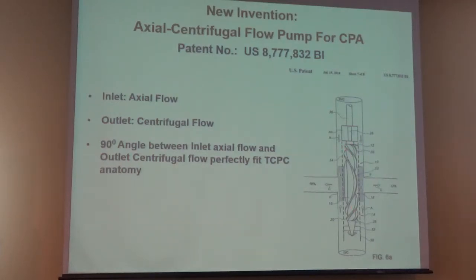When you pump, it runs very fast. So any kind of axial flow pump, HeartMate, anything, when you run very fast, they generate a centrifugal force very, very significantly. And then they will pump from here and here. Since the delta P in failing Fontan circulation is very, very small, maybe 10 centimeters of water, 10 millimeters of mercury makes a tremendous difference. So you do not need to run very fast to generate this pressure, delta P.